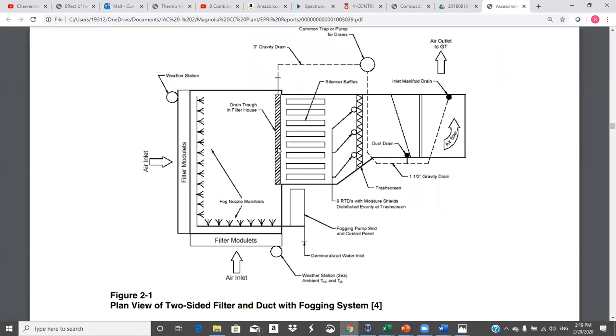So what do we have? So we've got air inlets, and it goes through the filters. And then we have these fogging nozzle manifolds where, you know, they want these droplets really fine. If the droplet's too big, it may still be liquid when it gets into the compressor, and it'll slug the compressor. So you got to have really fine droplets, and they want distilled water to make sure that you have clean water.